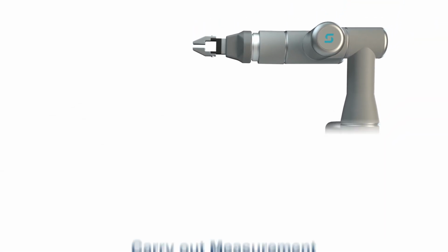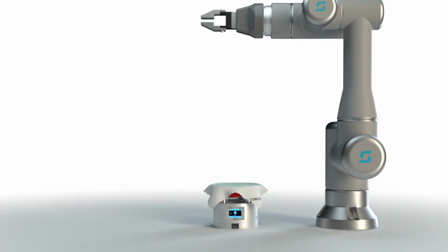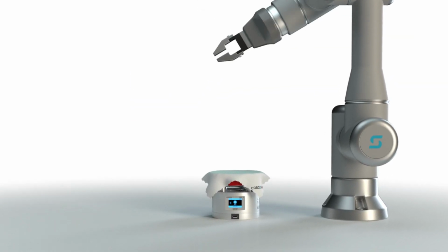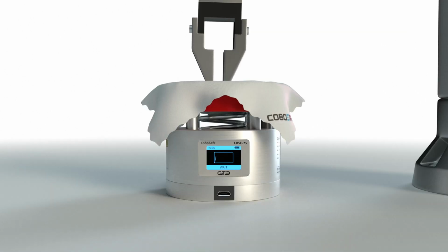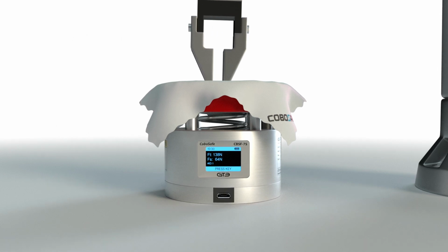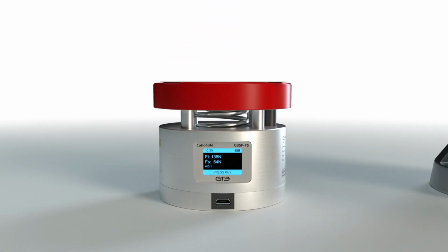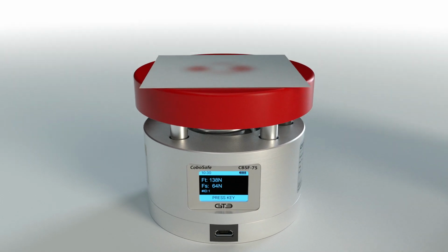Now, carry out the measurement. Make sure that the robot performs a safety stop during the measurement and that only safety functions are activated. The measured forces can be read directly on the display. The corresponding pressure is detected by the measurement film. The film turns red due to the pressure. The stronger the red discoloration, the higher the pressure.